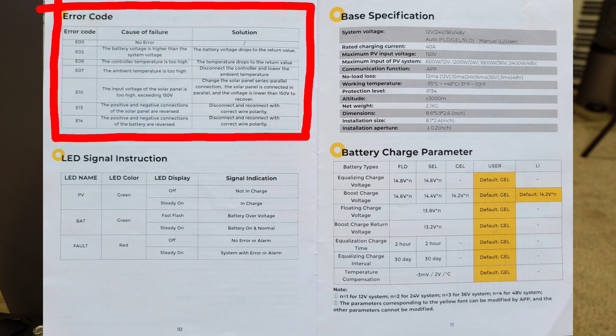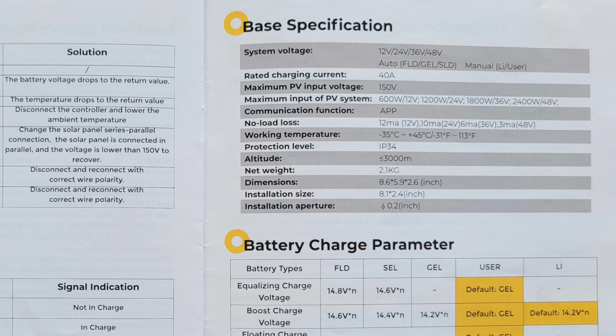On the last pages, 10 and 11, you'll see there's a chart for the error codes, so if you ever get one, that'll tell you what it's trying to say. Then here are the specifications - as mentioned, it's rated for 40 amps charging current, and its maximum solar input voltage is 150 volts. The no load loss is also important, only 12 milliamps - it's going to trickle 12 milliamps consumption from the battery if I'm not putting any load on the system, which I'm currently not. So right now I'm consuming 12 milliamps just to run the charge controller. Be aware of that.